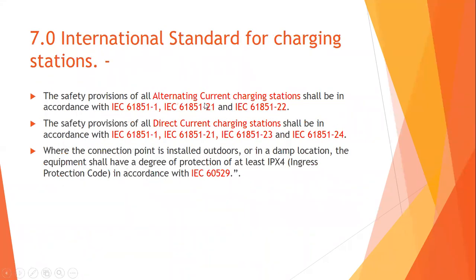Rule 7 covers international standards for charging stations. The central government is largely depending on international standards while the Bureau of Indian Standards continues research. For AC charging stations, IEC 61851-1, IEC 61851-21, and IEC 61851-22 shall be followed. For DC charging stations, IEC 61851-1, IEC 61851-21, IEC 61851-23, and IEC 61851-24 shall be used.